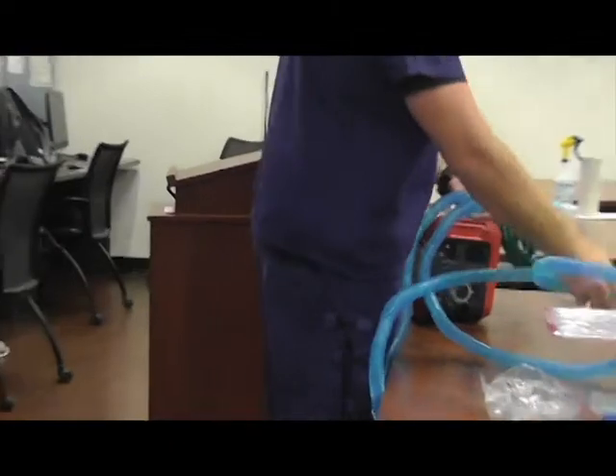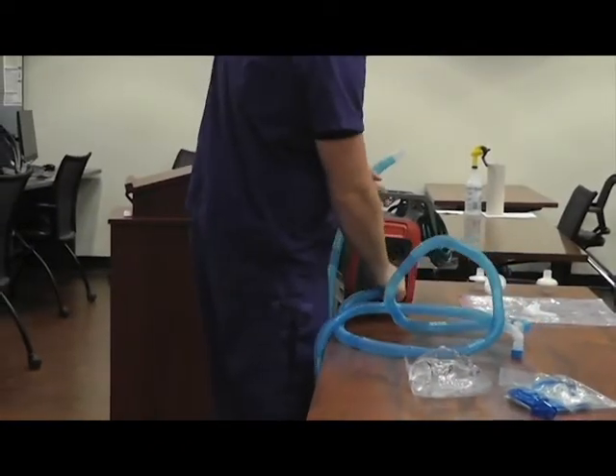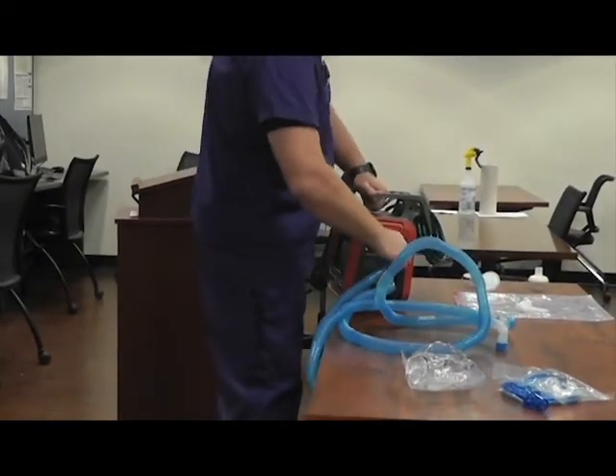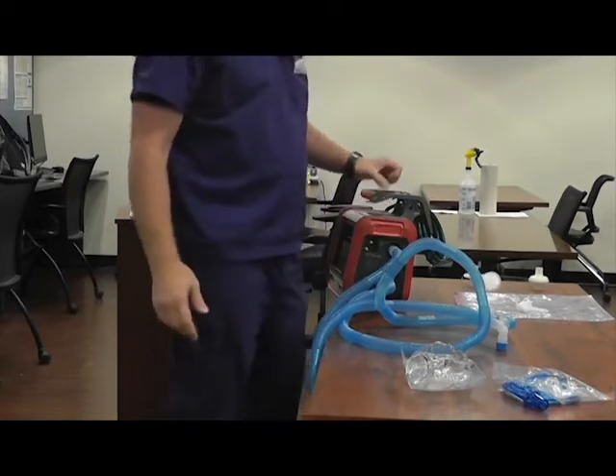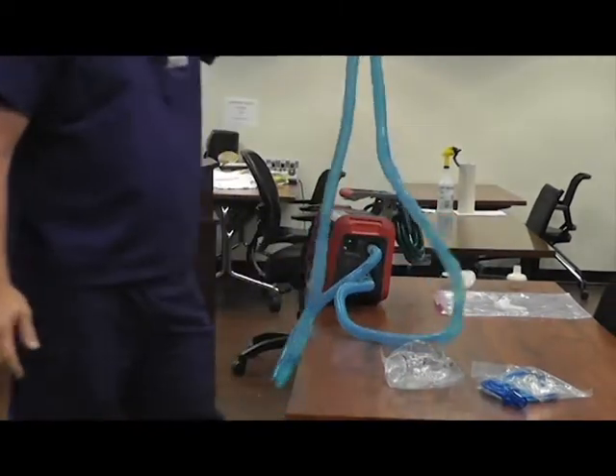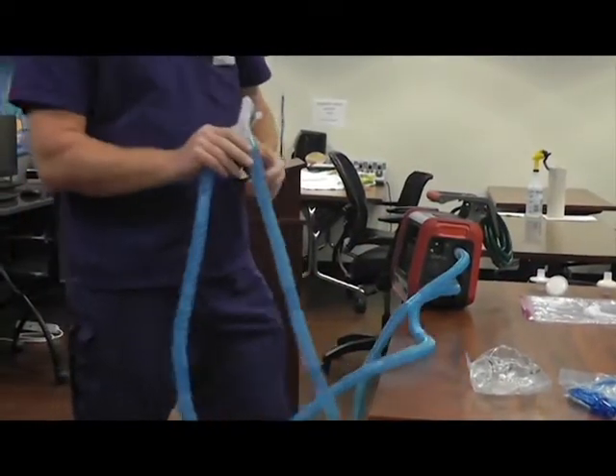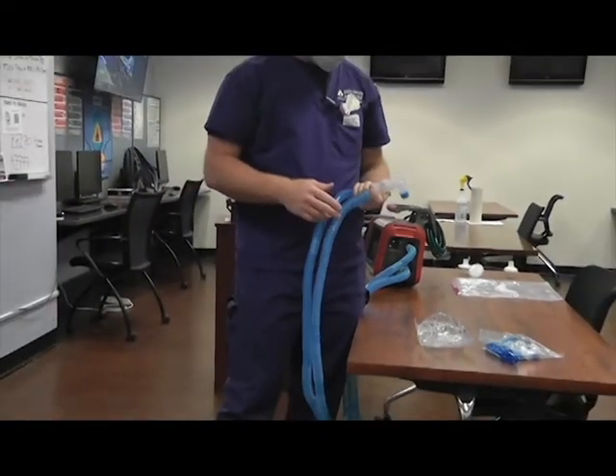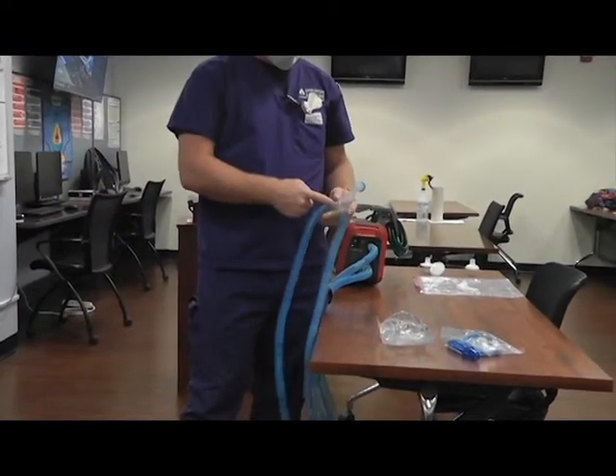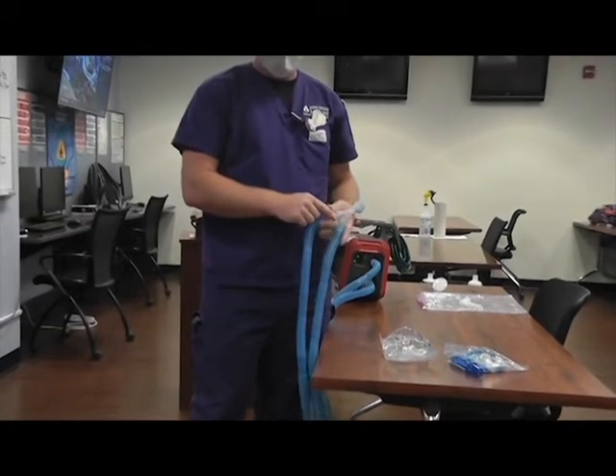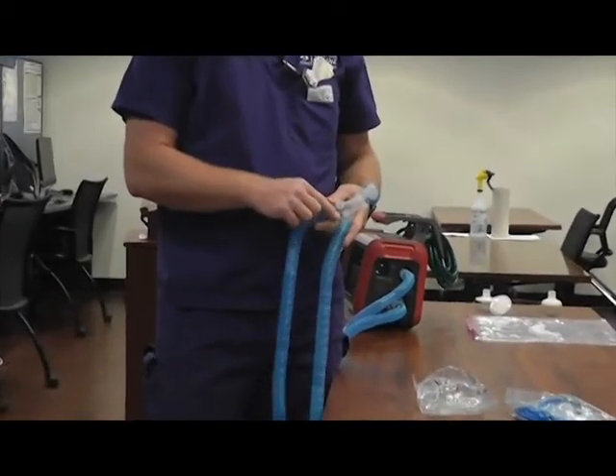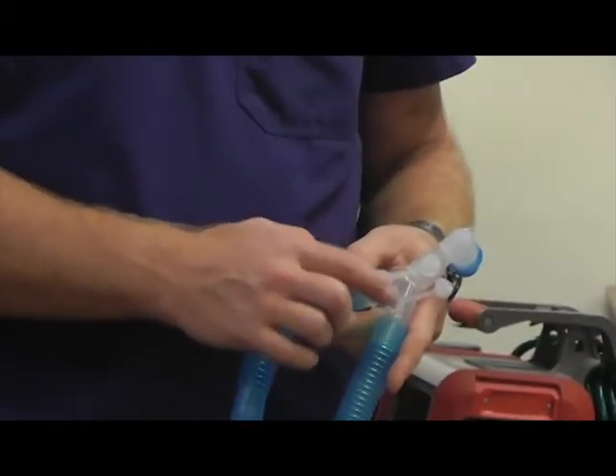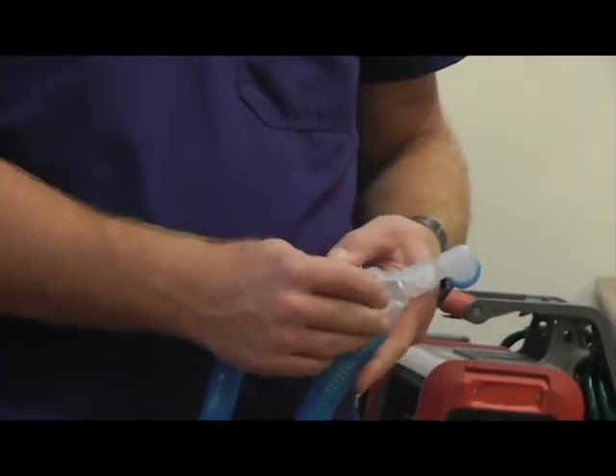It doesn't matter which limb is which on here. So just pick one limb, they're both the same. Put one on the exhalation port, one on the inhalation port. Big key thing here, and you will fail seal tests, things like that. This ventilator circuit was set up for heating, humidification wires, things like that. So there's going to be two holes. You just need to cover those holes with the caps.